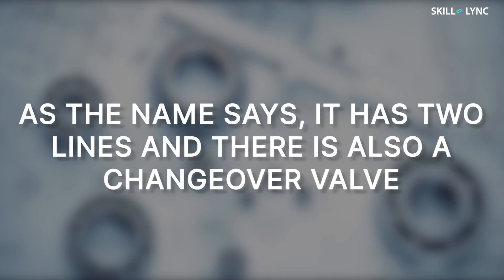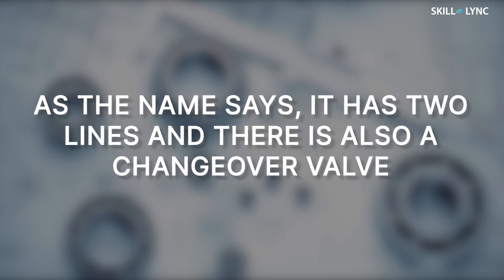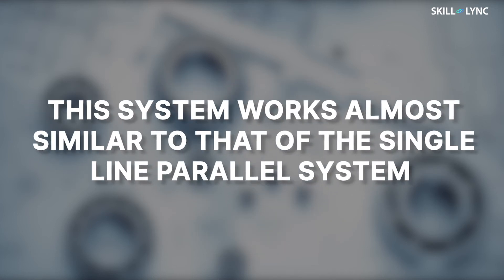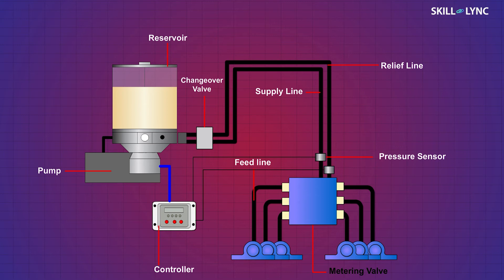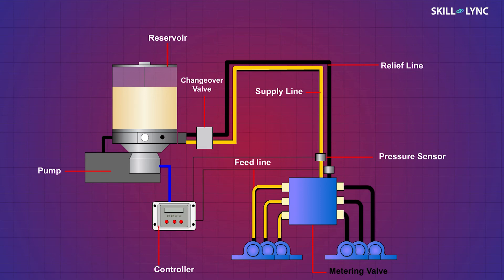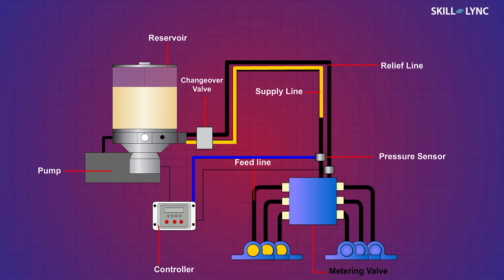As the name says, it has two lines, and there is also a changeover valve to switch connections between these lines. This system works almost similar to the single line parallel system. When the controller activates the pump, the lubricant gets pumped through the first line and the second line acts as a vent line. Once sufficient pressure is attained, the metering valve supplies lubricant to half of the total points.